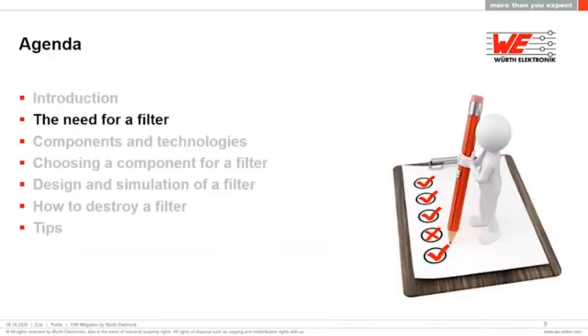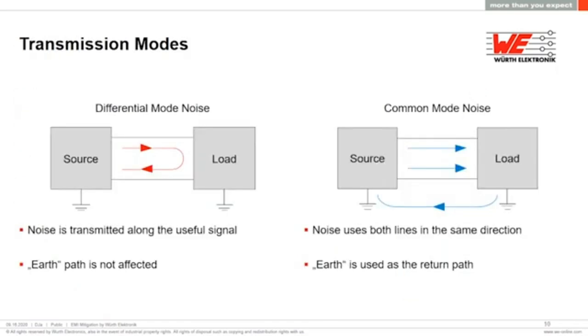Now let's move to the next section: the need for a filter. There are two types of noise in transmission modes: differential mode noise and common mode noise. The differential mode noise flows from one phase or one line to the other line; in this case, the earth path is not affected. For common mode noise, the noise flows in both lines in the same direction and the return path is to earth. That makes a big difference between the two modes.